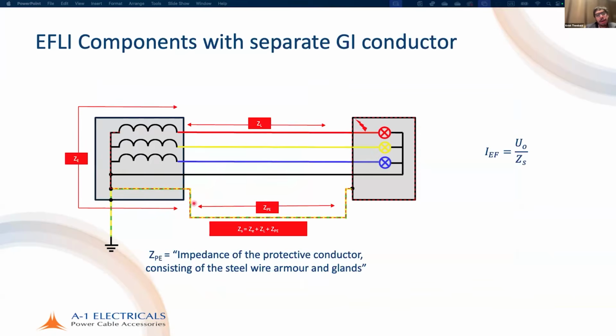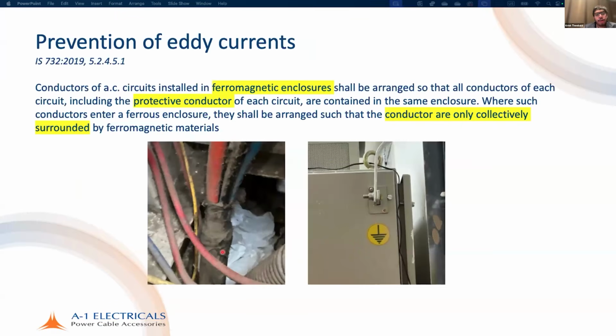First problem: the path of the protective conductor is now entirely different from the path of the line conductors. So the impedance of the protective conductor is particularly high. Normally, Zp would be the impedance of the protective conductor consisting of steel wire armor, and this no longer applies. This Zp will have a very high reactive component as well, due to the spacing from the actual line conductors. Additionally, we have a big inductive loop, and it is particularly harmful in terms of electromagnetic interference. Lastly, the GI strip itself does not have a particular resistance value, and there is no proper way to make a joint there that is standardized. So it is particularly dangerous and much more expensive. You have to buy all this GI in addition to the armor that you're already buying anyway, which comes as part of the cable.